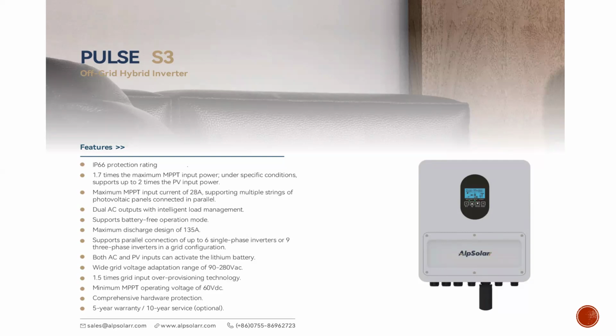The next unique selling point we have is that it has dual AC output with intelligent load management. So our inverter has two load outputs. The first one, which we call load one, is for the critical load. This is where you put all the essential loads, and you can be rest assured that power will constantly be supplied to all of the loads connected to load one. Then it has another load, which is called load two. That is another port. We call it smart load, where you put all your non-essential loads, depending on the client. For some clients, the air conditioner is a non-essential load. They don't need it all the time. For some, it's their washing machine.